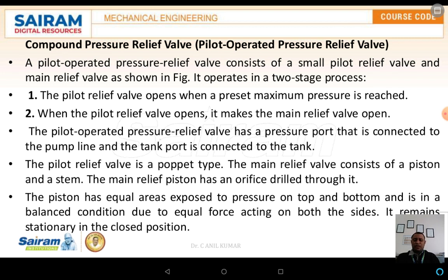The same pressure is built up on the pilot. Once the pressure is built up on the pilot, the pressure capacity on the line also increases. The main difference between the simple pressure relief valve and the compound pressure relief valve is that the compound valve consists of two different types of valves: the first is the main relief valve, and the second is the pilot relief valve.